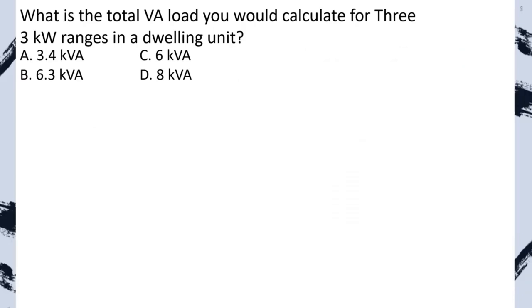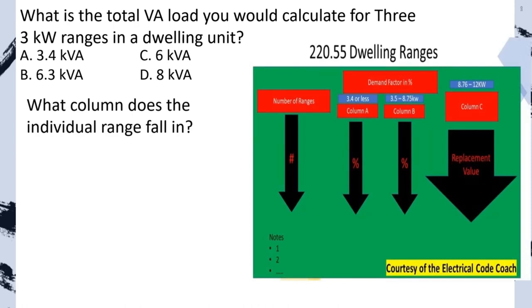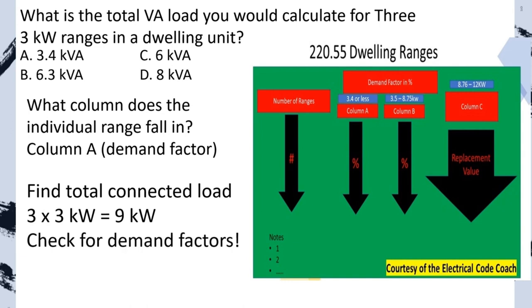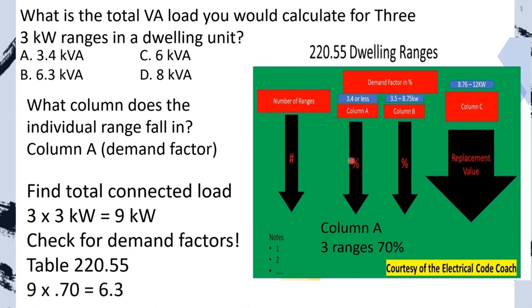Practice problem: What is the total VA load for three 3 KW ranges in a dwelling unit? What column does our individual range fall in? It's 3 KW — Column A, so we'll be applying a demand factor. Find total connected load: 3 ranges multiplied by 3 KW equals 9 KW. Check for demand factors: from the left-hand side find 3 ranges, cross to Column A, the demand factor is 70%. Multiply: 9 KW multiplied by 0.70 gives our new reduced load. We select B.